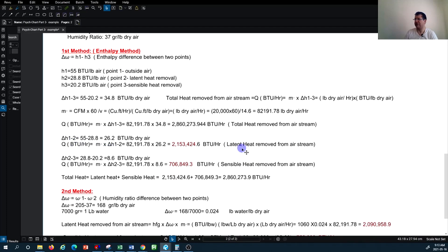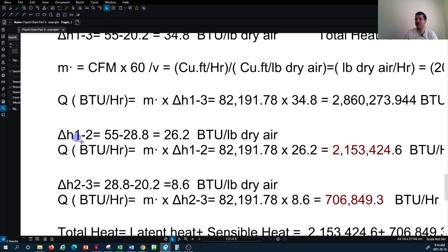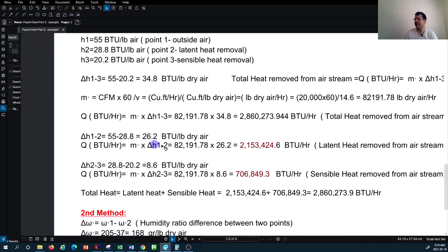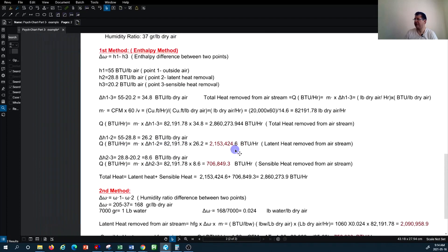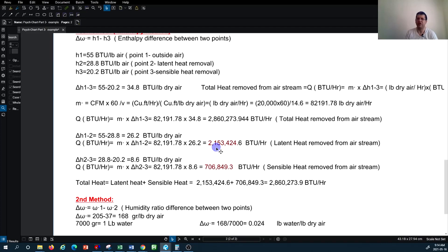For the latent heat removal, I repeat the same process but take the enthalpy difference between Point 1 and Point 2, then multiply by the mass rate of air to get total latent heat removal. The same process applies for sensible load using the enthalpy difference between Point 2 and Point 3. Summing the latent and sensible results gives the total heat load.